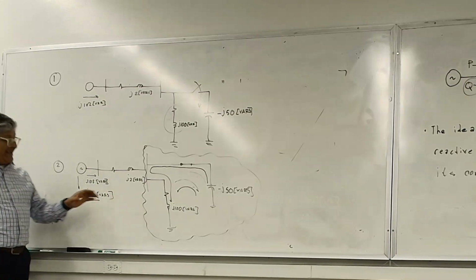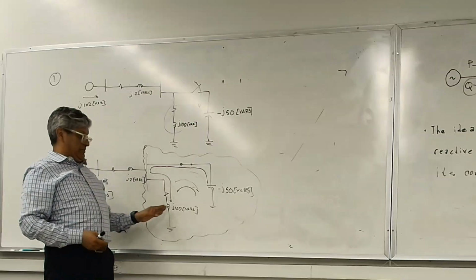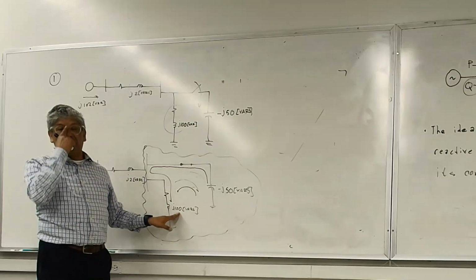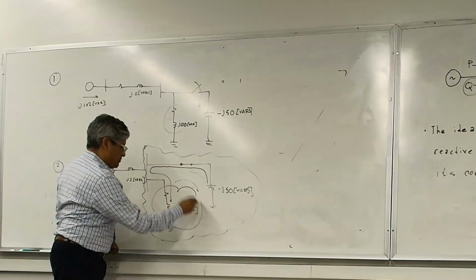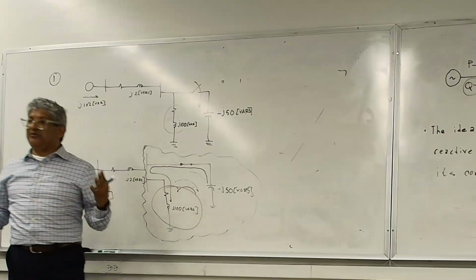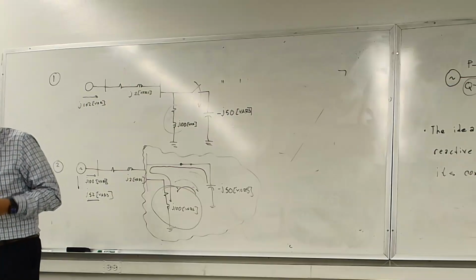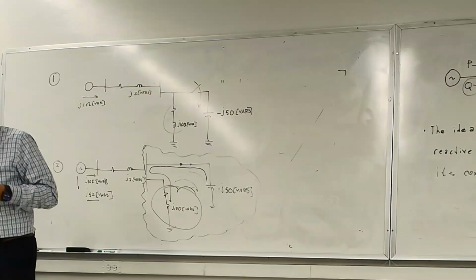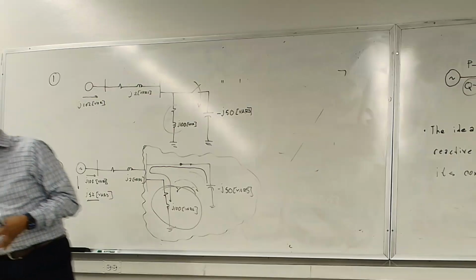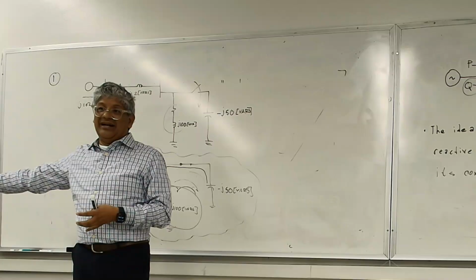So now, inside, you're still dealing with this. This doesn't change your motor. If this is an induction machine, the motor is consuming what it's consuming. You're not gonna change the behavior of the motor. What you can do by adding the capacitor and providing the VARs that the motor needs is tell the utility not to give you that.